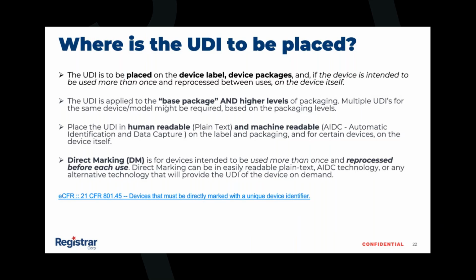The UDI is applied to the base package and higher levels of packaging. Multiple UDIs for the same device model might be required based on the package level. Okay, so your base package should have its own UDI. If you have 2 or 3 of your base packages in a carton, then that is considered a higher level of packaging, and that will also require its own UDI. Keep in mind, it will not have the same UDI as your base package. UDIs cannot be repeated. The GUDID will not accept it.